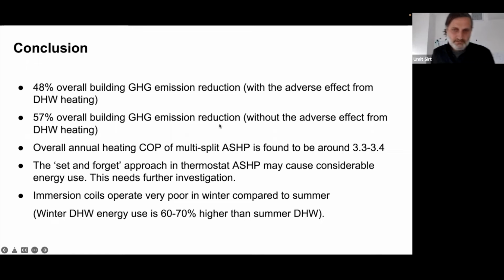According to our analysis, the annual heating COP is around 3.3, 3.4 for New York City. Here in Ithaca, what we see is 2.7, 2.8, and that is climate zone 6. The average temperature of New York City is about 42, 43 Fahrenheit in the heating season. Here it's about 35, 36 Fahrenheit. So I think it's reasonable, is my conclusion. And again, the set and forget approach should be investigated more. And we learned that immersion coils operate very poorly in winter, and the jacket losses and cycling losses of the boiler increase the use dramatically. Next, please.